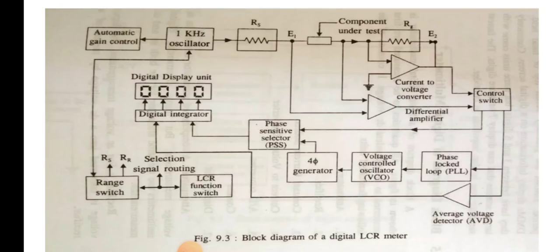The current-to-voltage converter is essentially an operational amplifier (op-amp) with a range resistor RG. You can see next to the component under test there is a resistor — that is RG, the range resistor — connected in the feedback path of the operational amplifier. This op-amp drives the junction of the component under test.